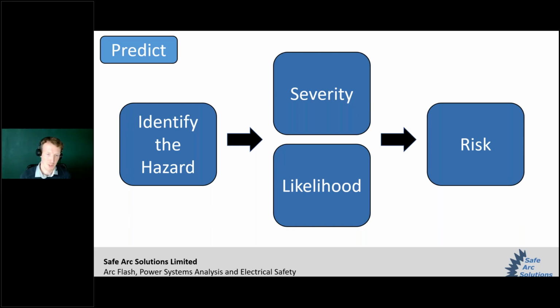Once you've identified the arc flash hazards, it's a case of risk assessing them. The usual approach is determining the severity of the arc flash and the likelihood of an arc flash event happening at any particular piece of equipment.